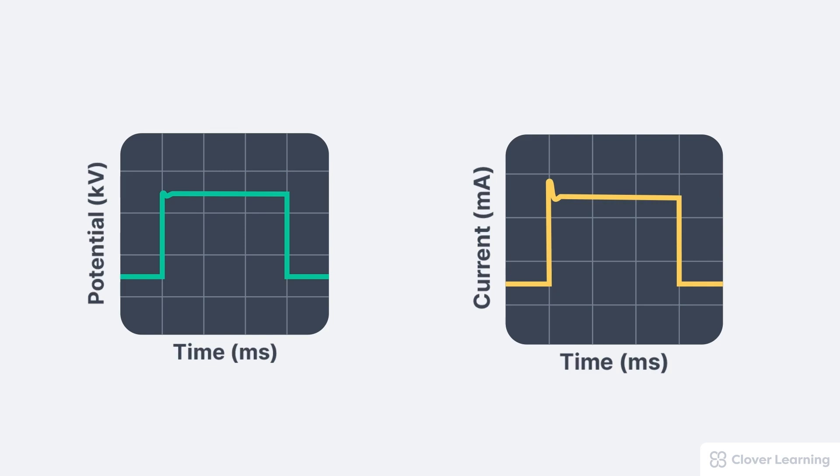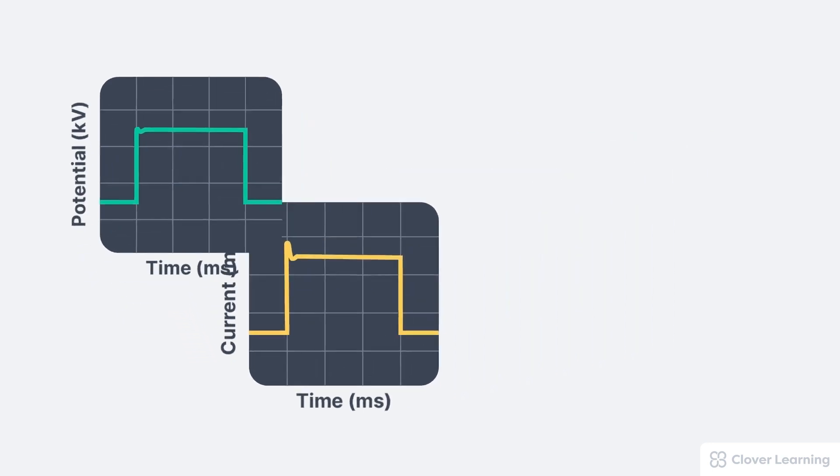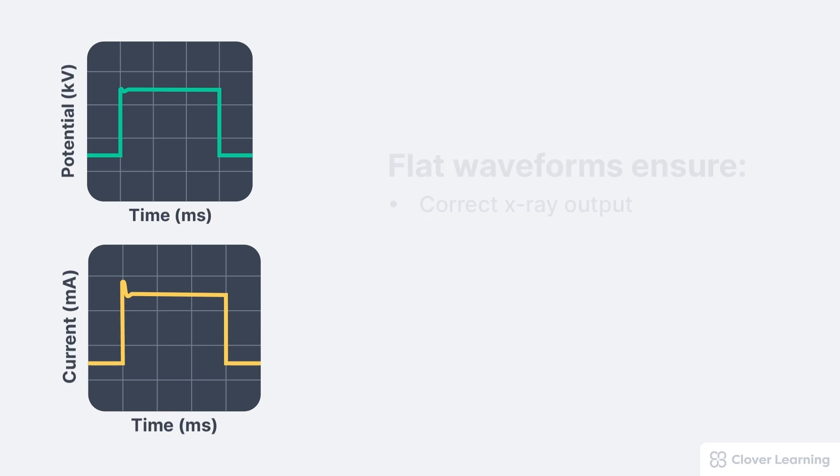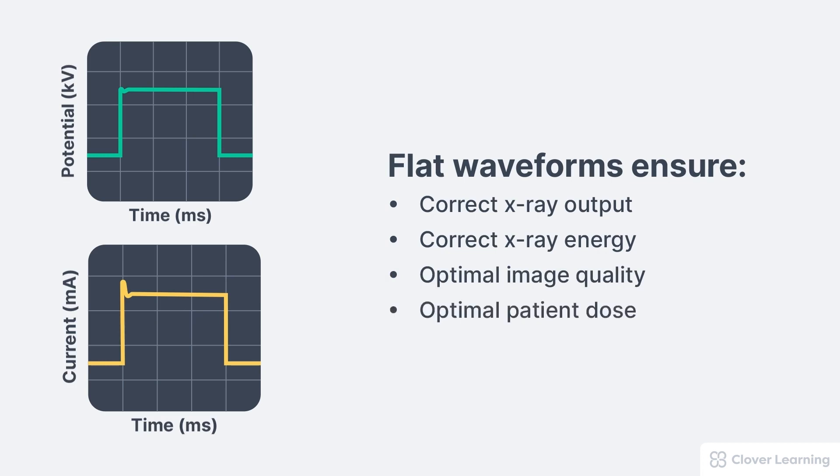When operating correctly, both the KV and MA waveforms should be stable and flat during the entire exposure. This is important to ensure the correct x-ray output, the correct x-ray energy, optimal image quality, and optimal patient dose.